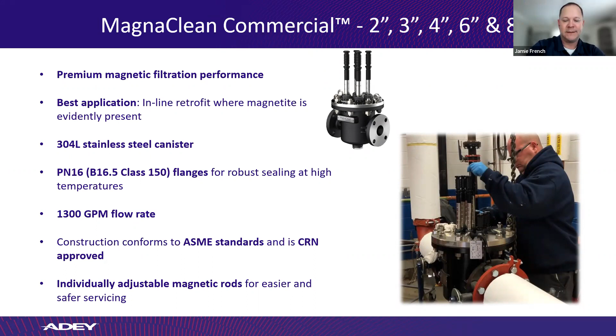But really easy to service here. Again, service in mind. We were invented by a pipe fitter to begin with, so he is very aware of how things are serviced. And you can see each one of these magnetic rods pulls up. So what you would do is isolate either side of the flange. You can have a blow down ball valve on the bottom there, 1.25 NPT, and then there's an air vent up top. So pulling those rods up, crack the air vent, open the ball valve, dump everything out, and then reverse it to get it back into service. 5, 10, 15 minutes max servicing this thing. Not only that as well, by having the rods, it means you're not breaking a seal by lifting the whole lid up. Correct. Yes, those are all individually sheathed in there. So you're just pulling it up and everything's dropping to the bottom of the canister. Thank you, Antonia. You're welcome. The DRX, this is 2, 3, and 4 inch.